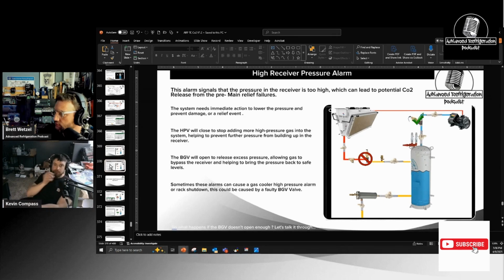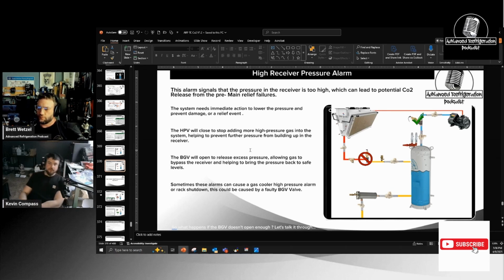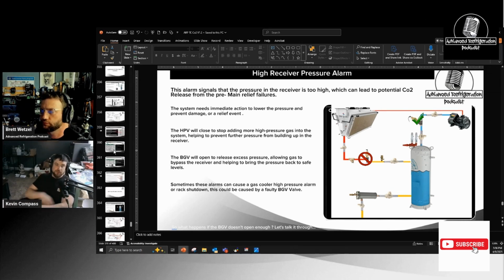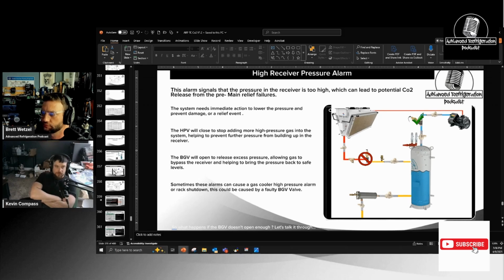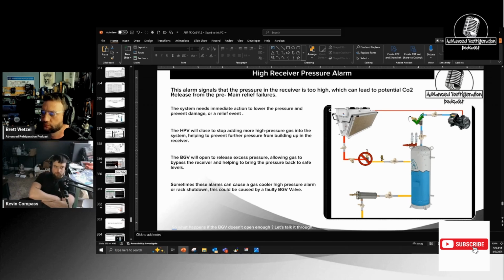So if you're low on gas, it hunts like crazy because it starts fighting the gas cooler and it tries to back up liquid into the gas cooler to maintain subcooling. When it's doing that, if you're low on gas, it doesn't have enough liquid to do it. So it ends up backing up more and backing up more and backing up more. Then you get this like terrible hunting.